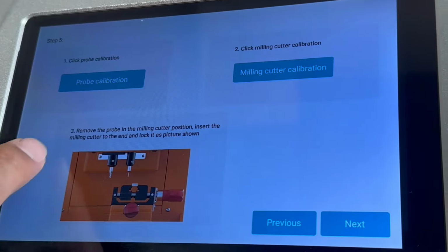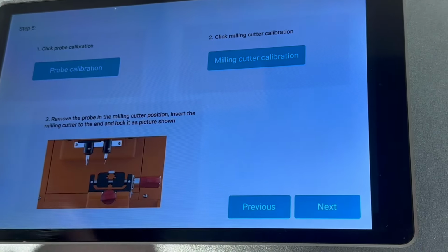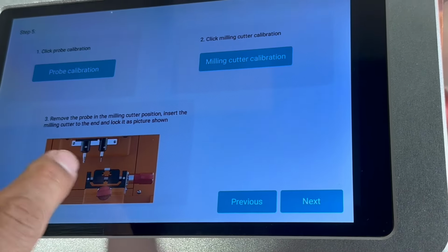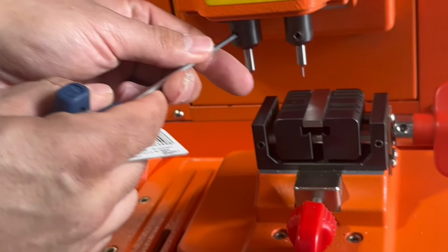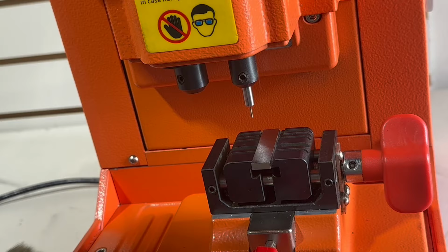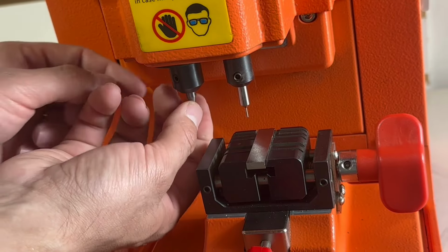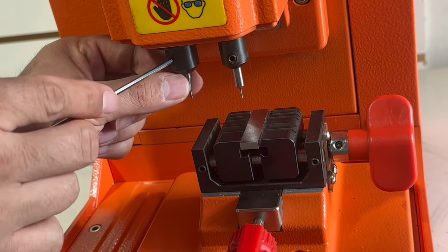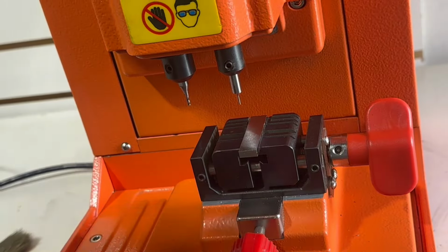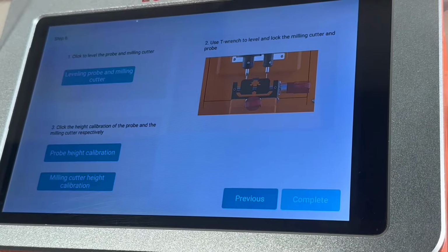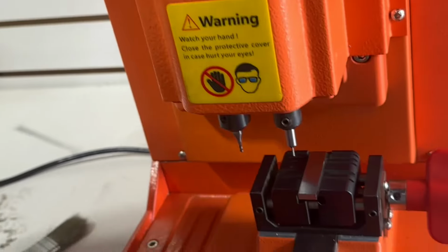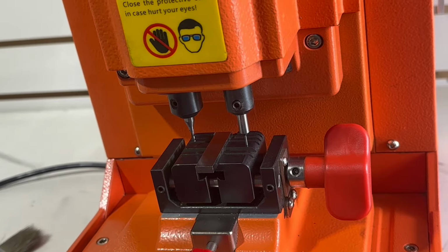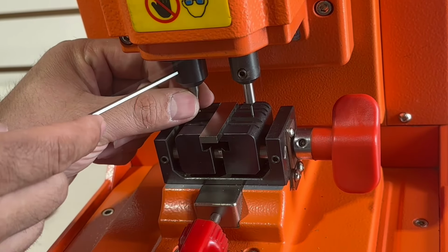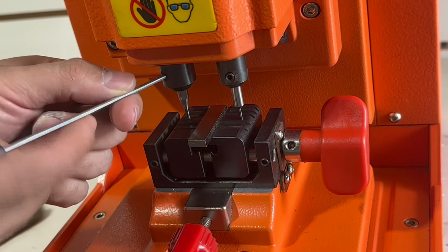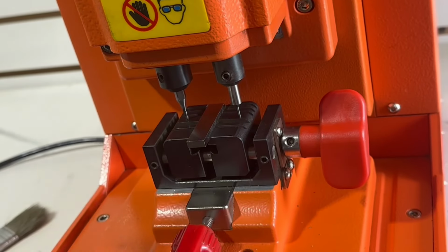Press OK. Next step is remove the milling cutter position, the probe that is we put a probe there, so we're gonna remove that one and we're gonna insert the milling cutter again. So you just go here, loosen, take it out and put your milling cutter. Make sure you put it all the way because it comes on the stage and you don't want it to damage. So and tighten a little bit. You don't need to tighten too much, just to hold it. Now it says next, you're gonna press next. It's a level, so now you have to level the milling cutter again. So leveling, again loosen, bring it down so it touches, make sure it touches properly, and then tighten again. So now we're fully ready to go for the next step.